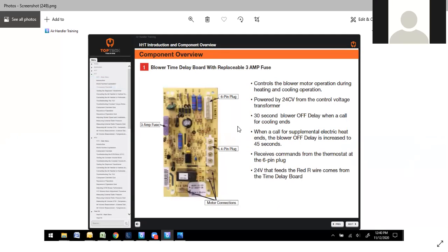A little bit different blower board here. You still got your 3 amp fuse. In this case, you have a 6-pin connection, 4-pin for your auxiliary heat. And if you look down here, you'll see where it says X13. These are your motor connections down here. So you don't have the big huge relay. You have motor connections right here, and these are going to be 24-volt connections.